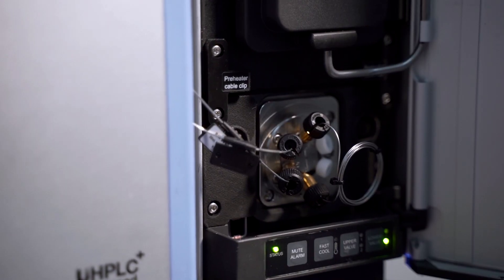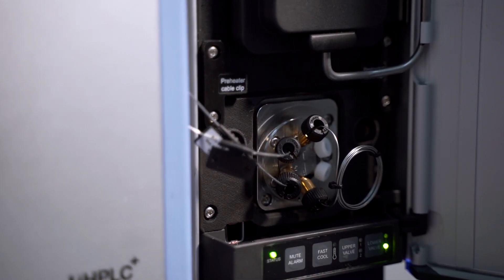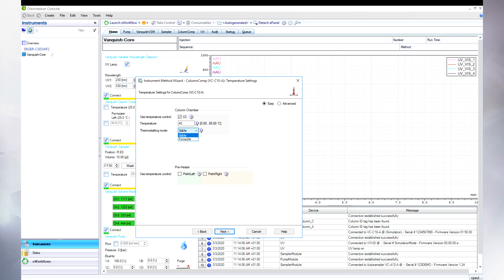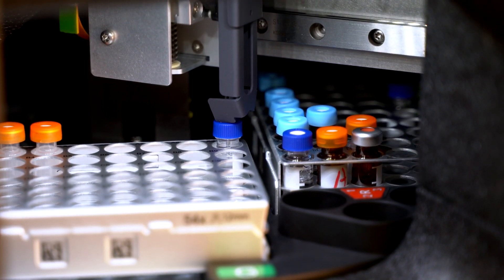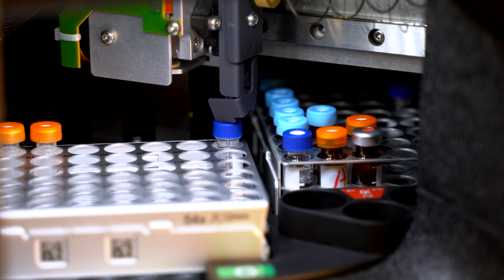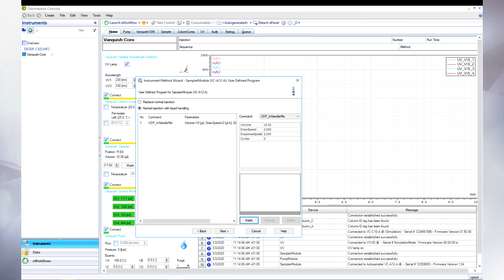In total, this allows us to adjust the gradient delay volume over a wide range without any modifications to the gradient table. Additionally, we have the only column compartment which can operate in two different thermostatic modes, which can be easily switched by a single mouse click. Last but not least, user-defined programs allow for in-needle dilution of strong solvent samples. This is a remedy for peak distortions due to solvent mismatches.